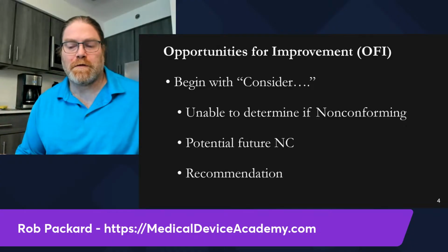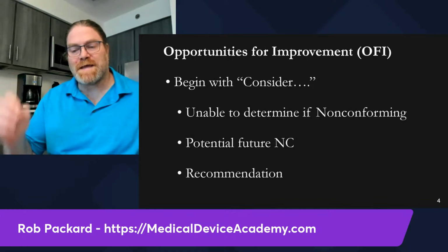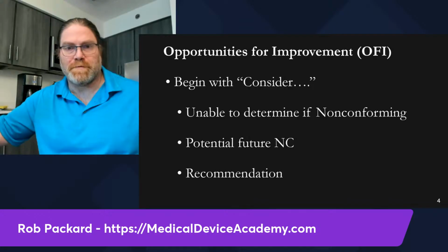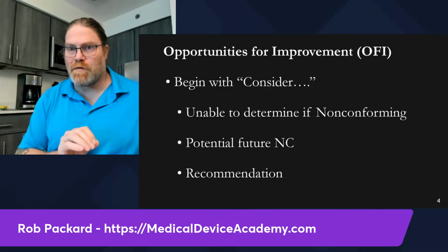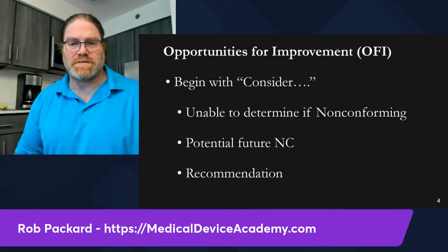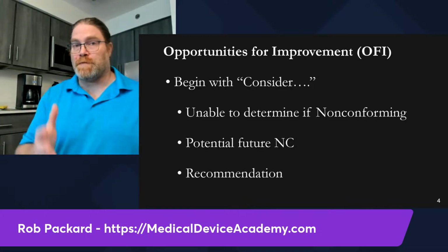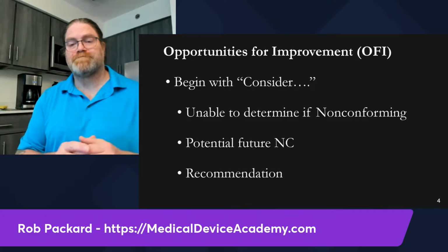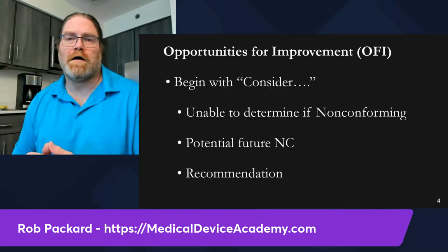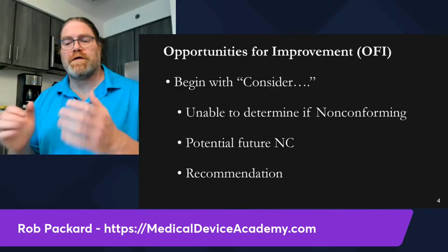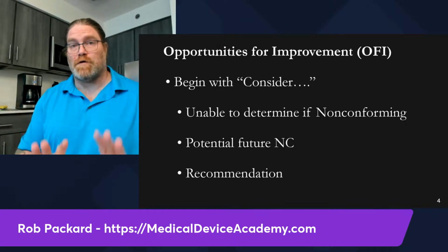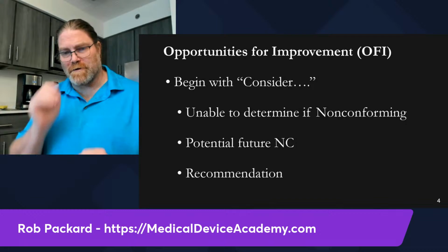And a good example of that would be, this is going to be a potential nonconformity when the QMSR is implemented February 2nd. So you don't have it now. You don't have this process or procedure. Let's say it's post-market surveillance. You don't have that now. You're compliant with the QSR, but you're not compliant with QMSR, which comes in on February 2nd of next year. So therefore, it's a potential future nonconformity, and that's why I've graded it as an OFI. That makes it really clear.